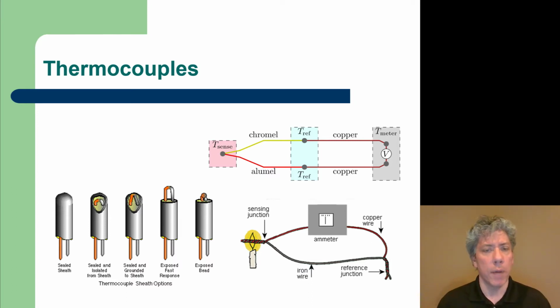Now, one of the problems with the sheath is that it adds a lot of thermal mass, and so it takes longer for the junction to come up to the temperature to measure the temperature of, say, a flame or whatever, maybe a liquid that it's inserted into. A sealed sheath, while it protects the thermocouple, does increase the response time. So it takes longer for the thermocouple to respond to changes in temperature.